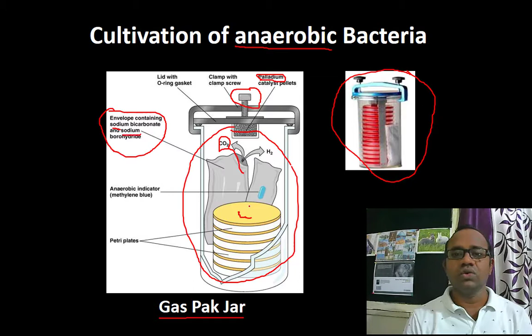Okay, we generally also use a palladium catalyst that helps in the creation of the anaerobic condition inside the jar system. Okay? So simply what we are doing is inoculating the bacteria onto the Petri plate, keeping those Petri plates inside the jar, and then closing it tightly with this knob. The chemicals inside the jar create the anaerobic environment, as they produce carbon dioxide. This can be helpful for the growth of anaerobic bacteria. That means they create anaerobic conditions. They remove the oxygen from the system and produce carbon dioxide. So this is an instrument for the growth of anaerobic bacteria.